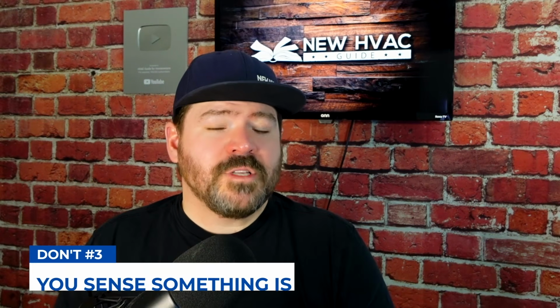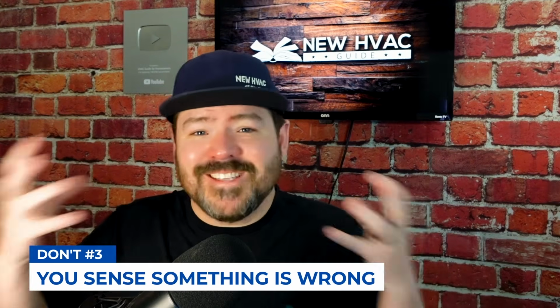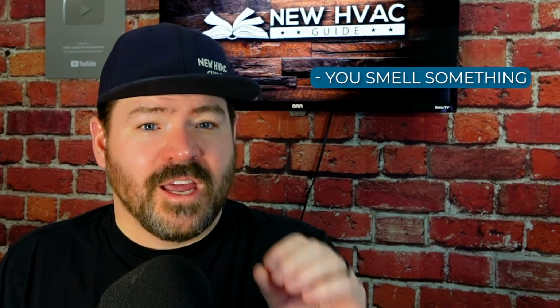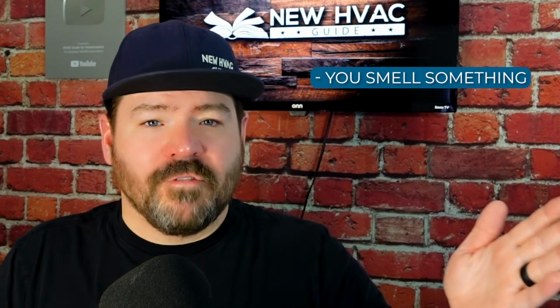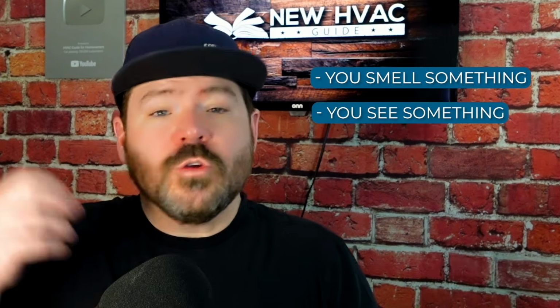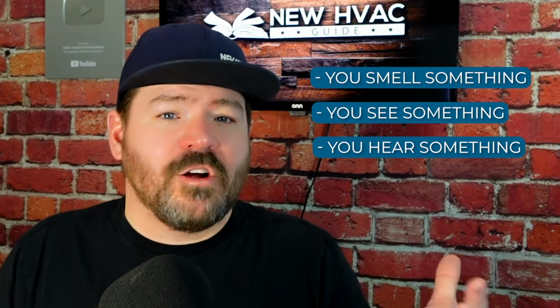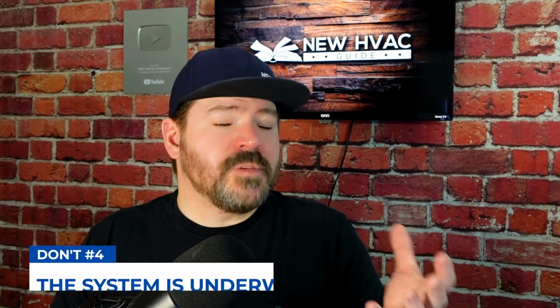Number 3, I would say your senses. So if your senses have sensed something wrong, meaning you smell something, right? It didn't just break down. You now smell whatever the odor is that you smell. Or you see something, I saw this happen. Or you hear something, I heard a loud bang, or I hear a clicking noise. Yeah, I'm resetting it. If your senses are picking up something other than the system just keeps turning off, I would not be resetting that system. If I'm hearing something or seeing something that's not normal, smelling something I'm not used to smelling, I'm not resetting that system.